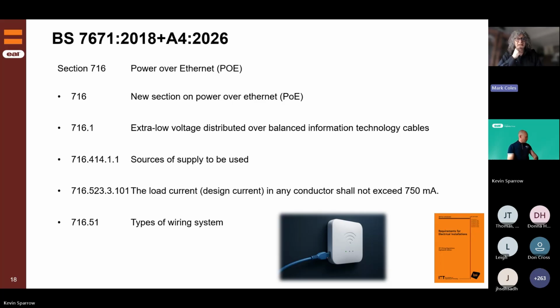So Power over Ethernet, as it says there, in the scope 716.1, extra low voltage distributed over balanced information technology cables. So it's those data cables. From memory, I can't remember if they're 4-pair or 8-pair, 4-pair, 6-pair. I think it's 4-pair, but you'll correct me on that one. But you'll know, is it the RJ11 or RJ45? I can't remember the type of connector. But within the section, it states what the BS EN number is for that type of connector. But it does say in there, as we get further down, the load current, design current of any conductor shall not exceed 750 milliamps. So that's where the design element comes in.